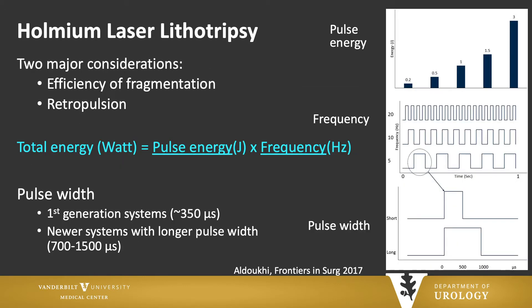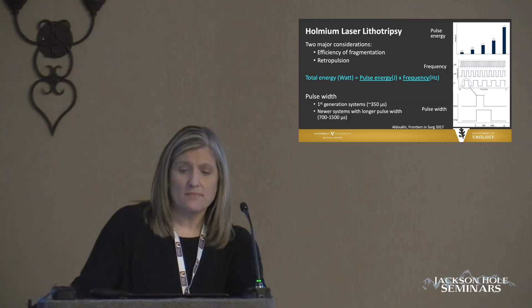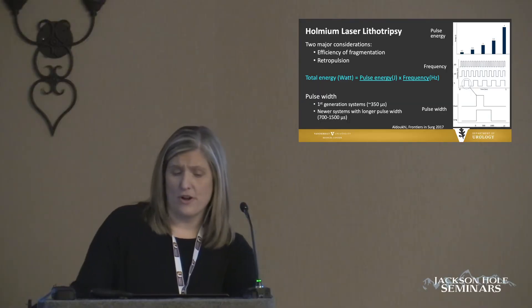There are two major considerations in Holmium laser lithotripsy: efficiency of fragmentation, and reducing retropulsion so that every pulse hits the stone as effectively as possible. When we talk about wattage — how much total energy you're giving — it is a multiplication of the frequency and the energy. So when someone says it's a 100-watt or 50-watt laser, or 'I used 10 watts for this case,' those two parameters are what you're controlling on your laser.